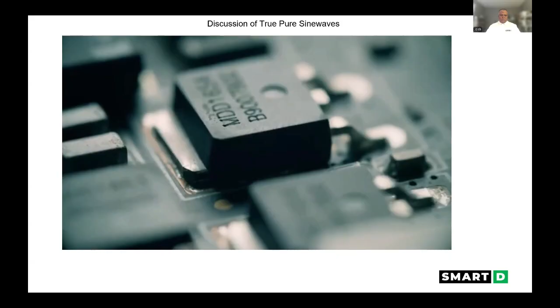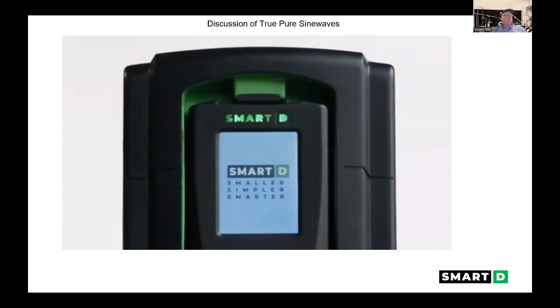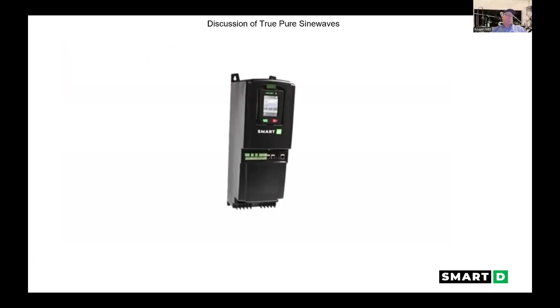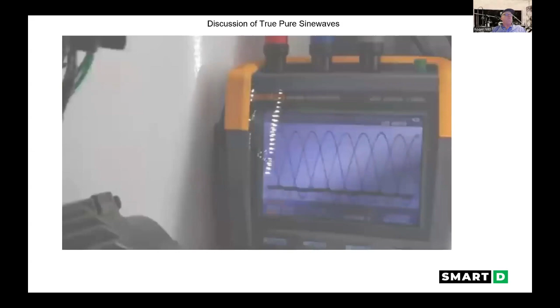Clean power takes advantage of the latest generation of power transistors, advanced algorithms, and optimized integrated filters to produce the next generation of VFDs without common mode voltage. A clean power VFD is the solution. A three-phase clean power VFD produces three smooth sinusoidal waves, which at any point average a sum of zero. This creates an optimal scenario with zero common mode overvoltage. The best solution to mitigate common mode voltage is to not generate it. A clean power VFD produces a clean signal with no need to mitigate common mode voltage.